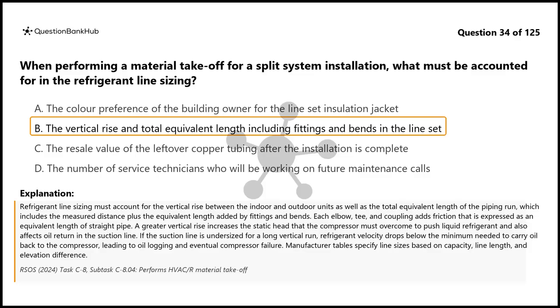If the suction line is undersized for a long vertical run, refrigerant velocity drops below the minimum needed to carry oil back to the compressor, leading to oil logging and eventual compressor failure. Manufacturer tables specify line sizes based on capacity, line length, and elevation difference.